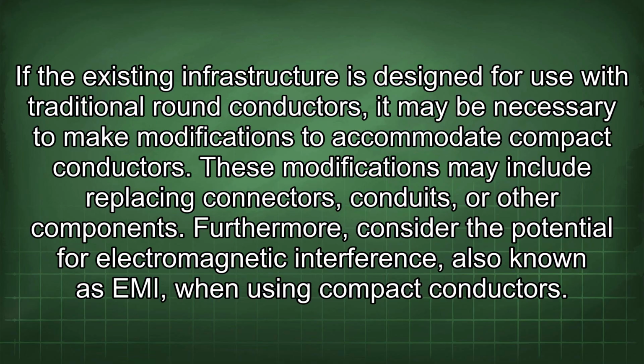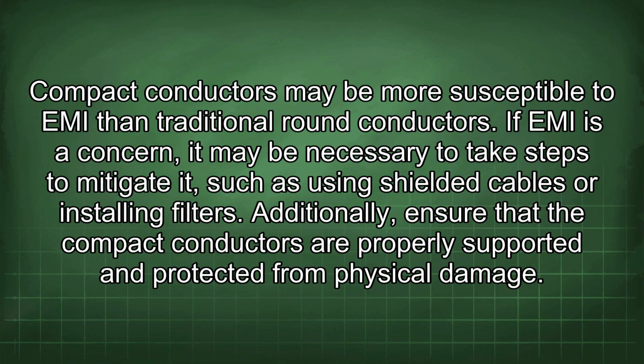Furthermore, consider the potential for electromagnetic interference, also known as EMI, when using compact conductors. Compact conductors may be more susceptible to EMI than traditional round conductors. If EMI is a concern, it may be necessary to take steps to mitigate it, such as using shielded cables or installing filters. Additionally, ensure that the compact conductors are properly supported and protected from physical damage.